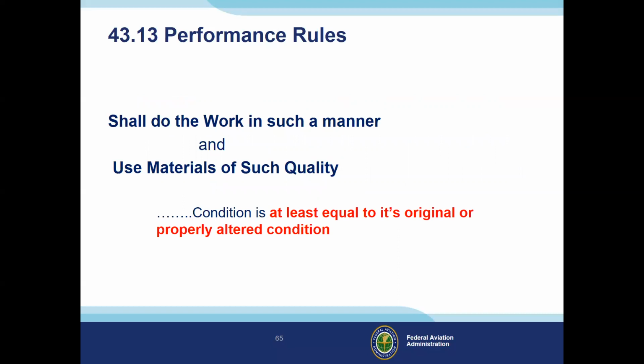You shall do the work in such a manner and use materials of such quality that the condition is at least equal to its original or properly altered condition. A good example is a bolt that comes from the factory torqued to 20 foot-pounds, and you over-torque it to 35 foot-pounds or under-torque it to 15 foot-pounds. You have violated the performance rule.